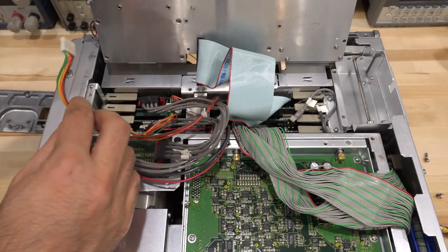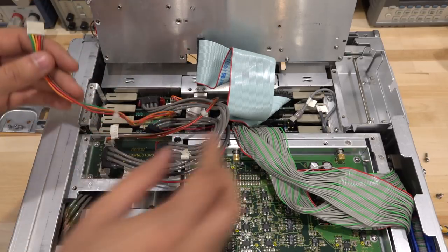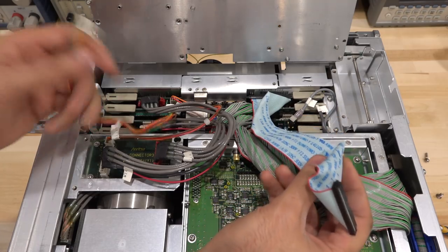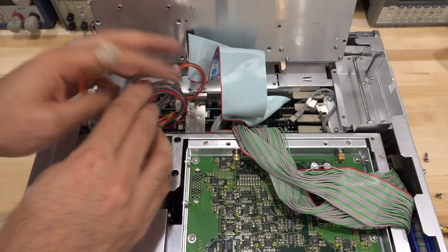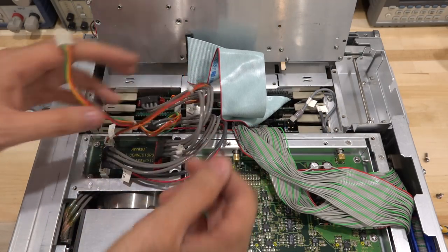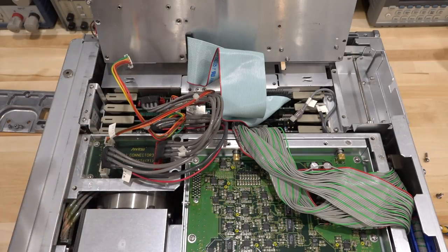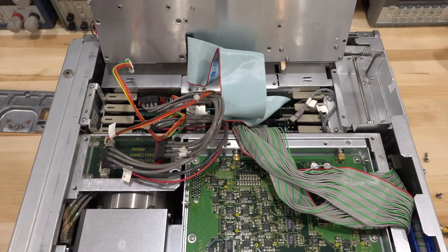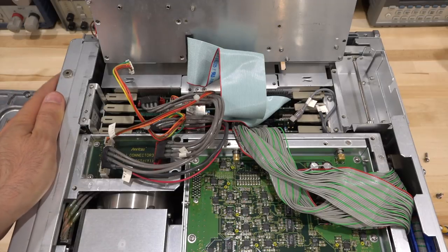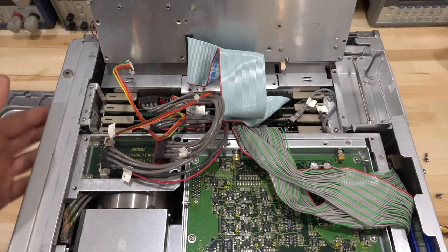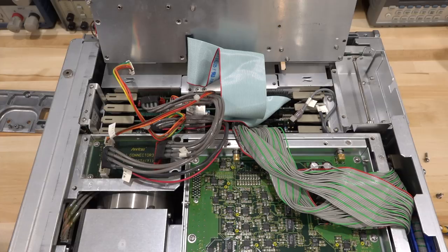This is just powering that optical reference module at the top. This is powering the printer and controlling the printer. And so what I would do, I'm just going to plug and unplug everything, reset everything, clean the connectors with the oxide cleaner, and then once all that, put it back together, turn it on, and see if it comes back to life. I would also like to change the backlight of this too, but unfortunately I don't have any more backlight strips left, so we'll see if maybe hopefully it'll arrive today. If it does, I'll do that.